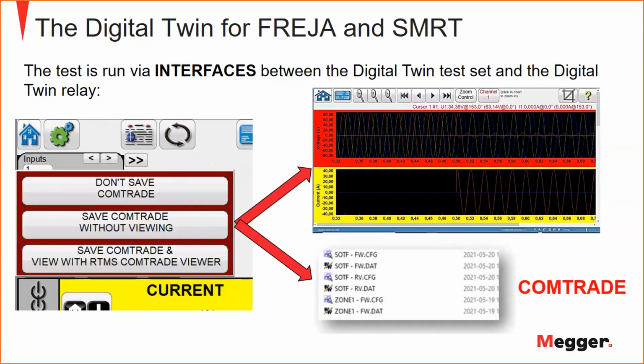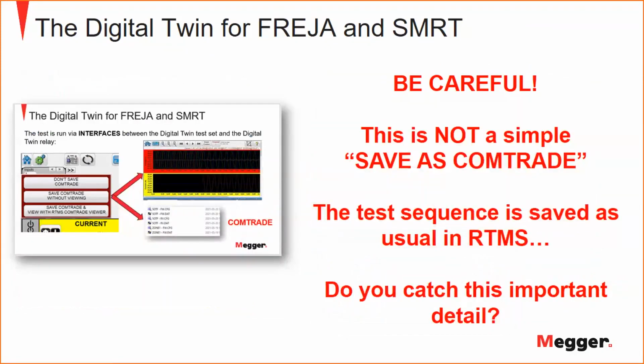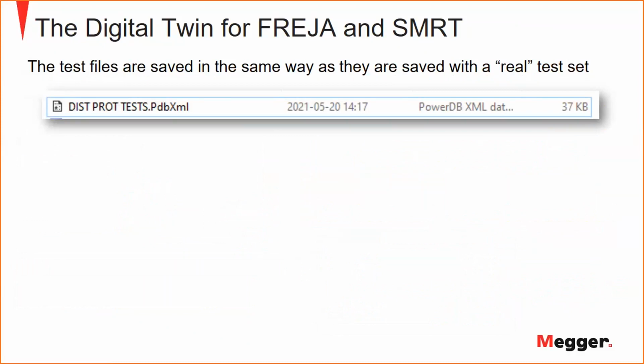That is what happens. You can have a preview with our previewer and then save it, or you just save it. And then that's all. But be careful, this is not the same as saving COMTRADE from RTMS. RTMS runs against a digital twin, which runs and also gives voltage and currents as it would do in reality. And the output is, at this moment, in COMTRADE. If you want the output in another way, we will fix the output in another way. It depends on what interface the digital twin is going to ask us.